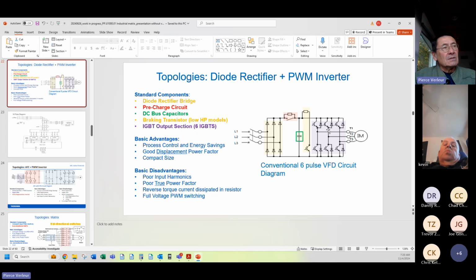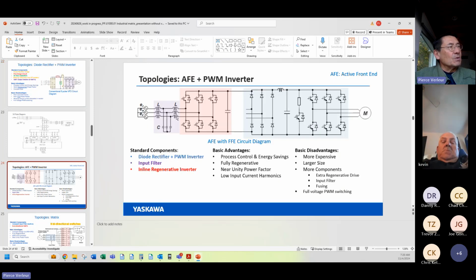And then the inverter section inverts DC back to AC. So we wanted to replace this static section with an active section so that we could then shape the waveform going back to the drive or to the power line and not distort the power line and not reduce the power factor. A la the active front end drive came out in the 90s. It's not innovative technology. It's the same technology as 1983, just with a section flipped around and connected. This section here, the original diode bridge, as you can see, is not connected anymore. It's just there for illustrative purposes of this diagram and actually doesn't exist in the active front end drive.